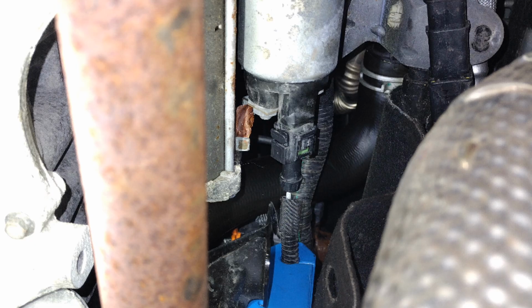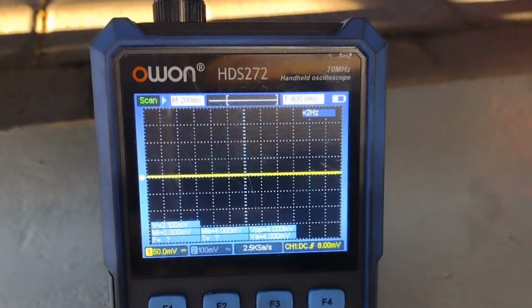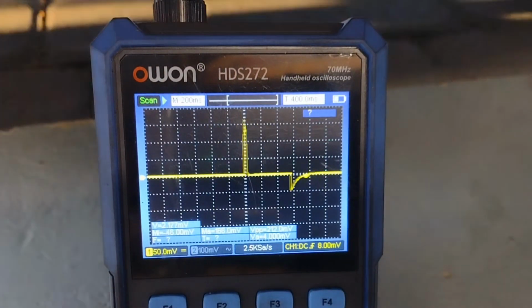I couldn't actually back probe it because the probe wouldn't go far enough into that connection, so instead we're going to use the amp clamp. I've got the amp clamp on a 10 millivolt per amp setting, and you can see there it's drawing about 5 amps.